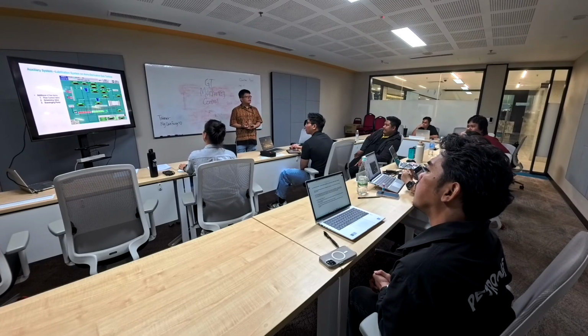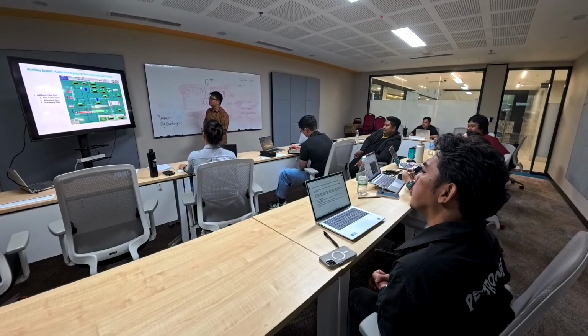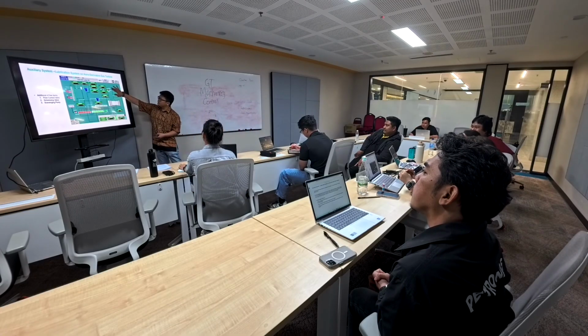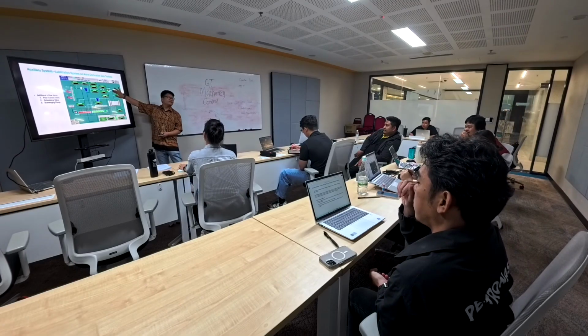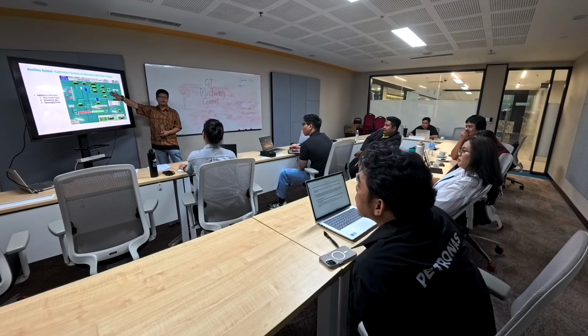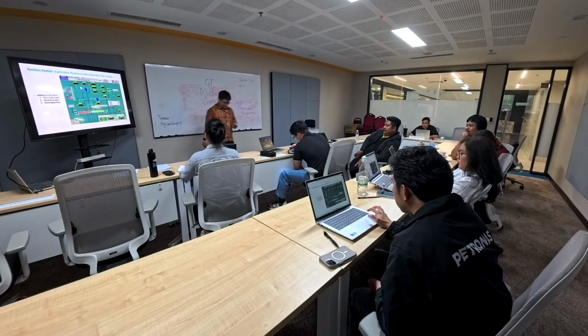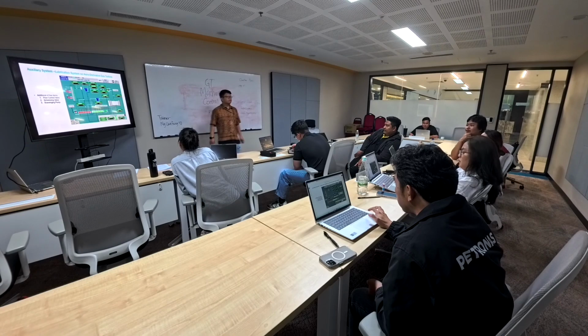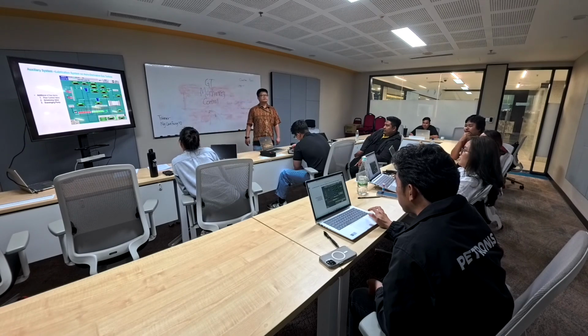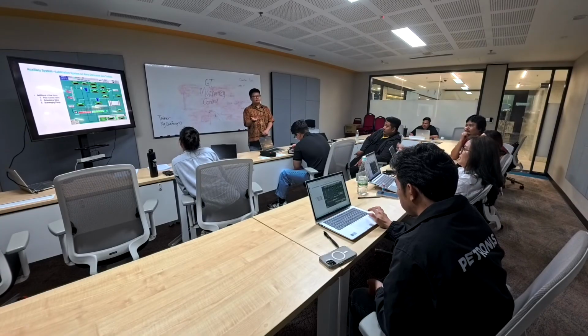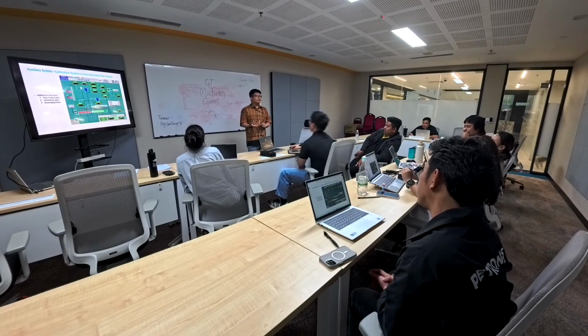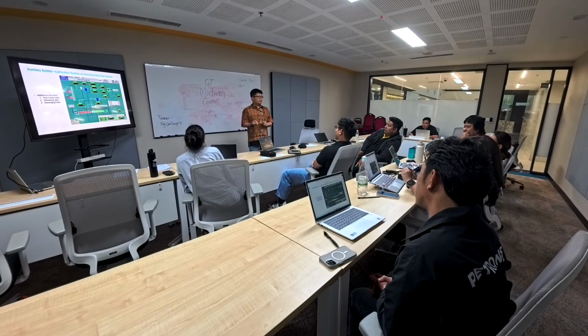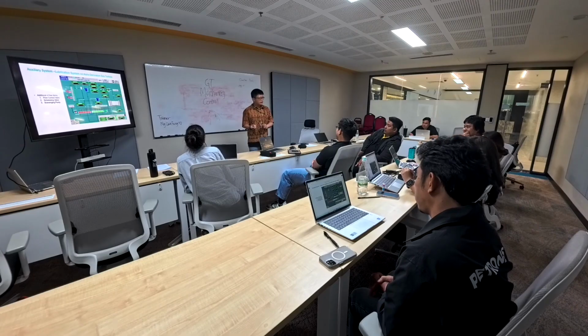So anybody want to explain? Try to explain what is scheduling. What is the purpose of scheduling? What is the function of the scheduling valve? We talk about the scheduling valve here. You have pre-wet, you have bypass, and you have schedule. 3 functions in this particular scheduling valve. To see the oil flow to the bearing. Okay, partially correct. The purpose of the scheduling valve is to make sure we have the correct amount of oil going into the bearing housing at different timing.